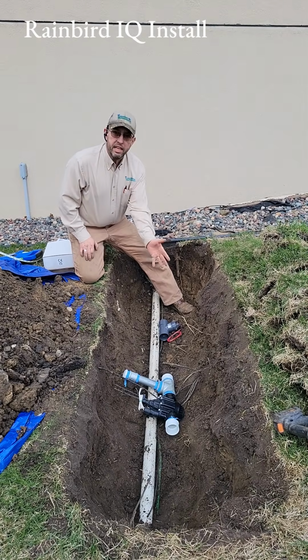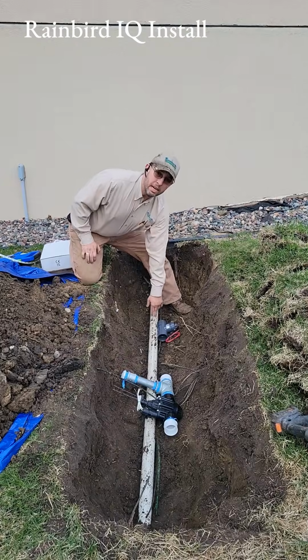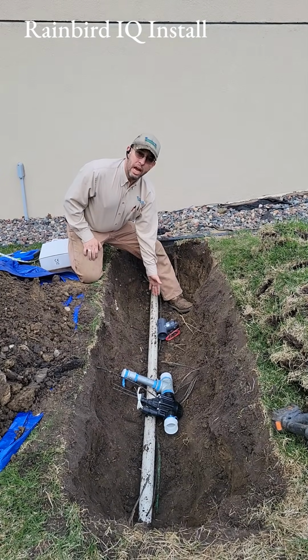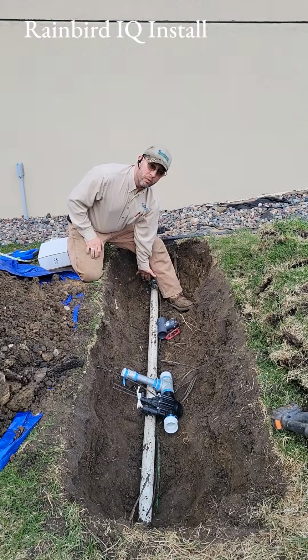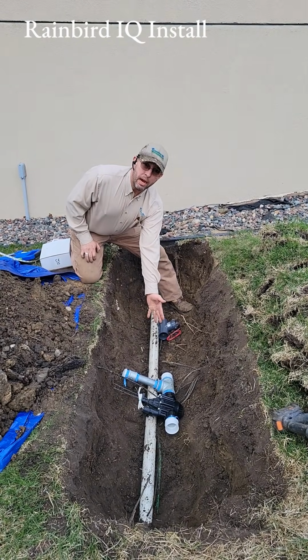Okay, we've got everything excavated out. The FlowMax sensor is going to go in. We have to have at least 20 inches of straight pipe before it and 10 inches of straight pipe after.